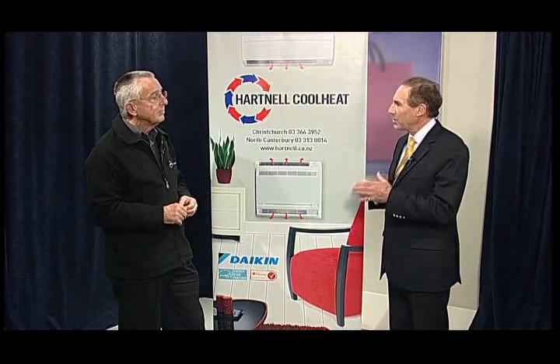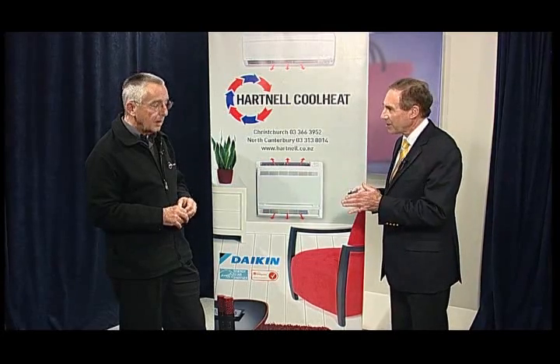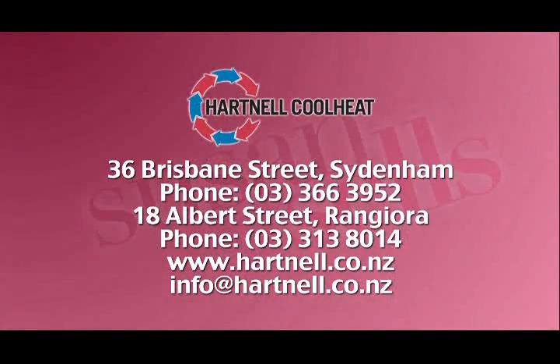So what we're really talking about, Graham, is volume to size of kilowatt. Is that correct? Yeah, absolutely. And another phrase we use, and it's very true, there is nothing worse than a heat pump doing a struggle. So if I come out with sort of 4.5 kilowatts, then we up it to something in the region of 5.7 because we don't know what's going to happen, but what we do know is if the weather really turns to custard, you need value for money.